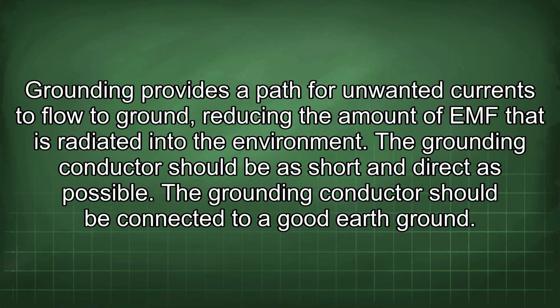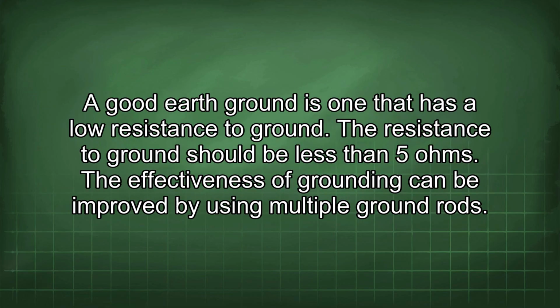Grounding provides a path for unwanted currents to flow to ground, reducing the amount of EMF that is radiated into the environment. The grounding conductor should be as short and direct as possible. The grounding conductor should be connected to a good earth ground. A good earth ground is one that has a low resistance to ground. The resistance to ground should be less than 5 ohms.